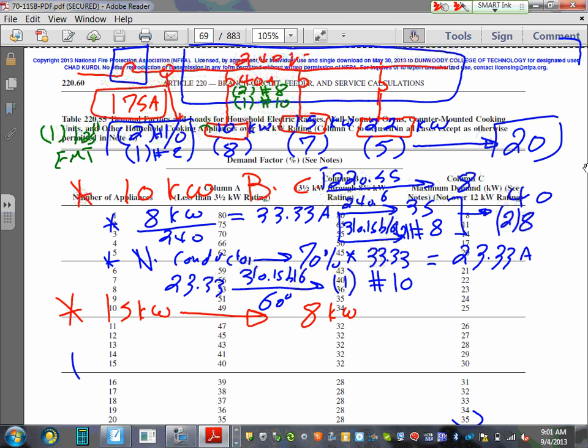Okay, the code says for branch circuit, apply the table. No problem, ranges. Okay, is the 15 kW less than 12? No. So the demand under C is 8, but because it's not less than 12, had it been less than 12, we're done. Because it's more than 12, you need to up this number 5% for every kW the demand is more than 12. Okay, that's step number 1. Step number 2 is you're going to take 15 minus 12. That will get you 3 kW. The third step is you take the 3 and multiply it by 5%, and that will get you 15%.